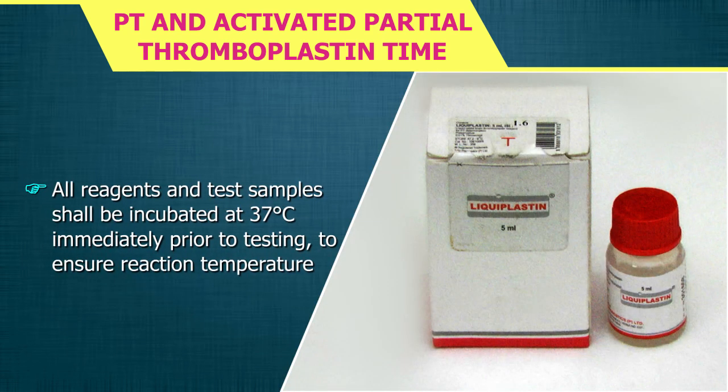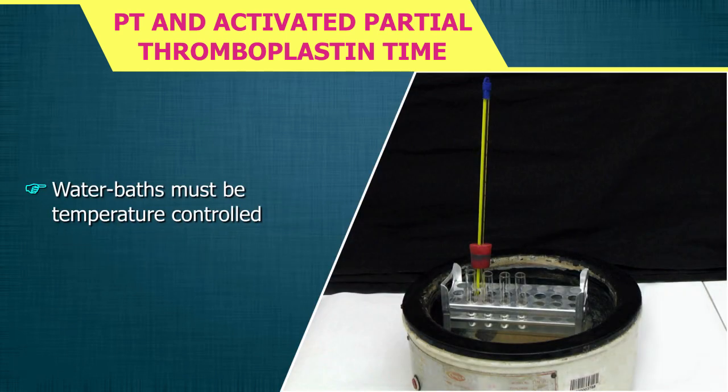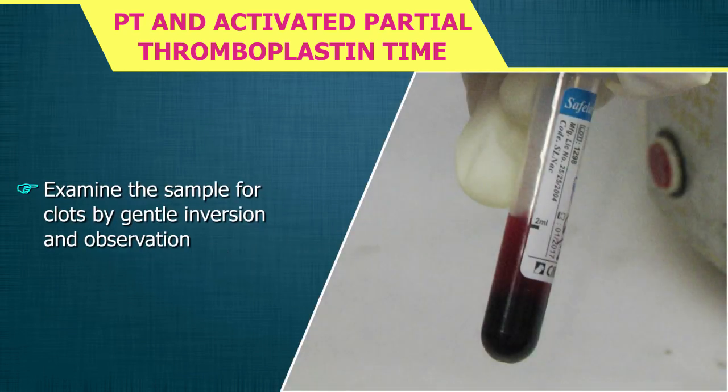All reagents and test samples shall be incubated at 37°C immediately prior to testing to ensure reaction temperature. Water baths must be temperature controlled, and timers shall be checked for accuracy at least annually. Carefully examine the sample for clots by gentle inversion and observation.